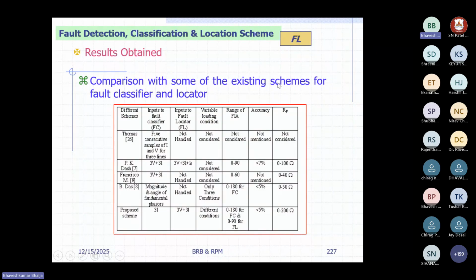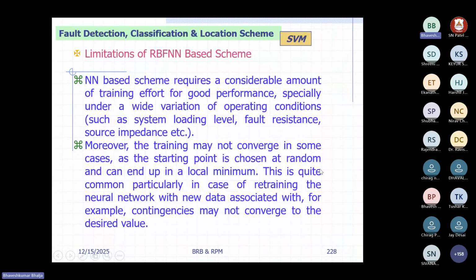And then I have compared with the existing algorithms for fault classification and the fault locator network. So you can see that the proposed one is better, right, in terms of the error and all that. Now limitations. I used a radial basis function based neural network. As I told you, the neural network requires a large volume of data, right? So you need to generate that. If data changes significantly, and if there is a wide variation in data, then your output also changes. And sometimes it is possible that when you go for training, your training may not converge, right? Because it may end up in a local minimum. So this is quite possible, right?